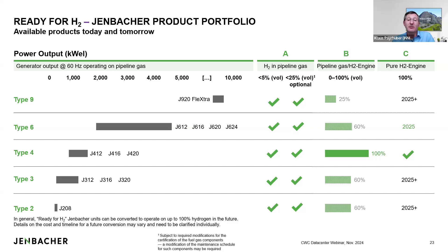So the next one is here. This is an example where we installed a hydrogen engine recently, a CHP unit in Korea, a 60 Hertz application. That engine is a 420 engine, can run on 100% pipeline gas, so natural gas, as well as 100% hydrogen, and has an output of 1060 kilowatt. In this case, it has the same output for natural gas and hydrogen, though typically the hydrogen output is about 30% lower than the natural gas output of that engine.